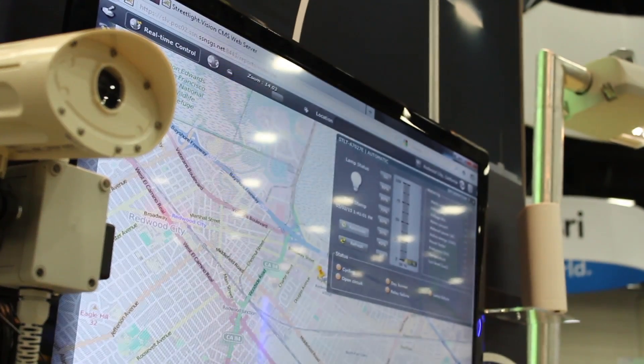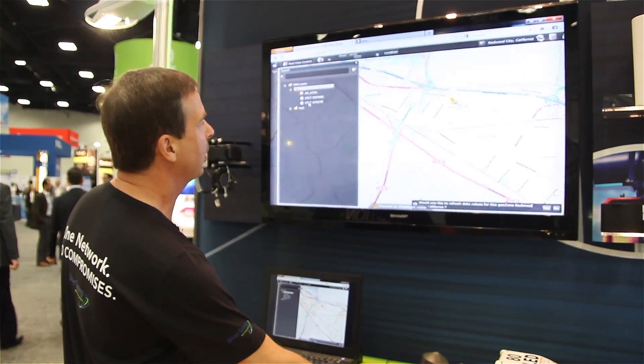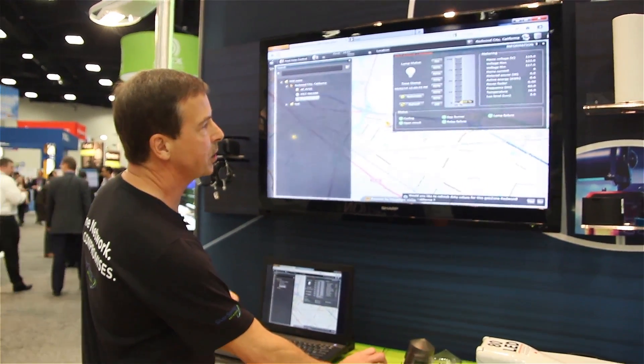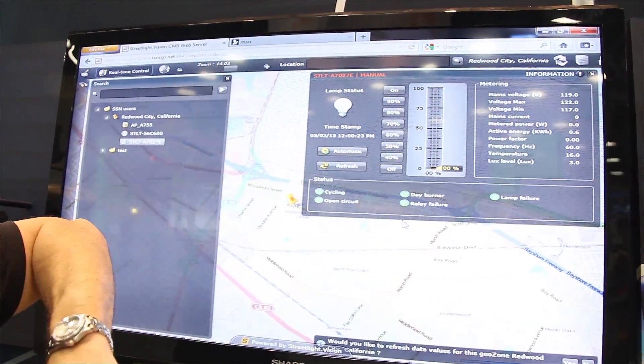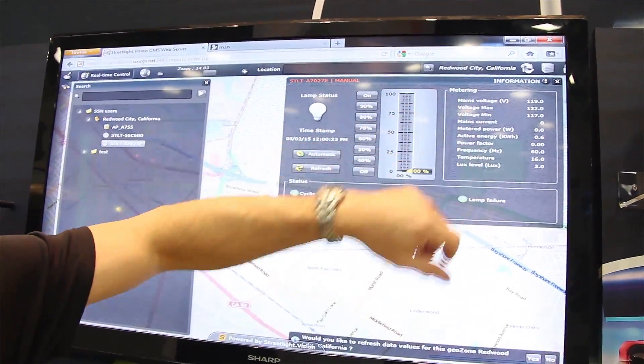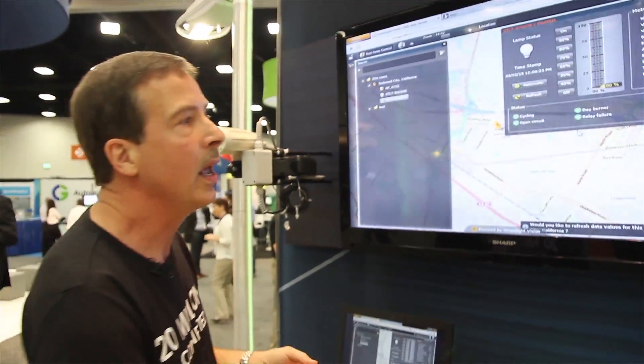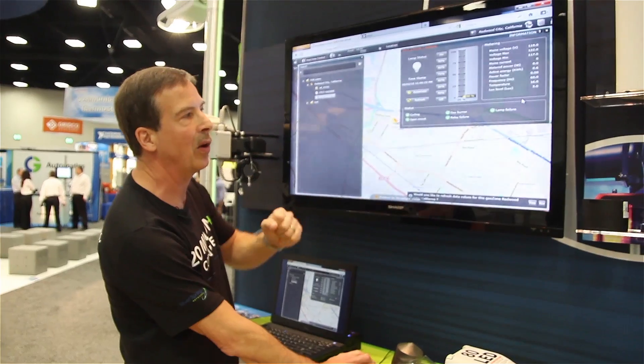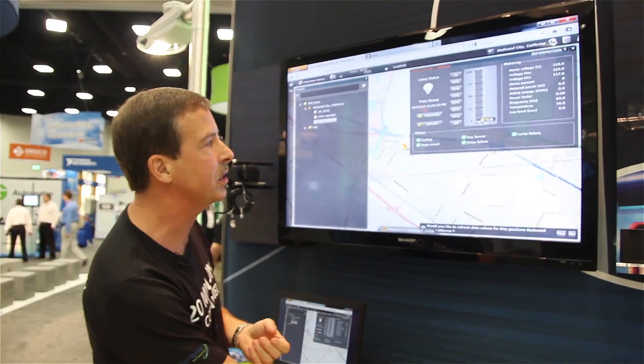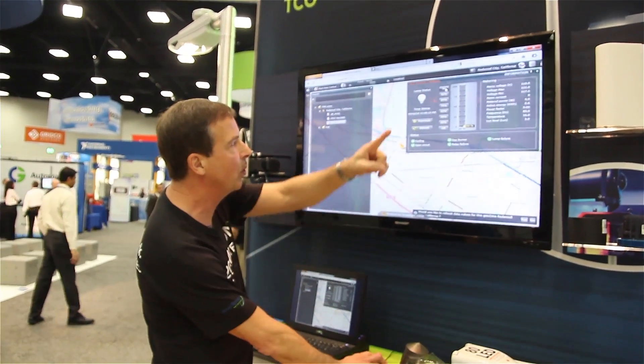We're going to click into the real-time control on this screen and identify the streetlight or group of streetlights we're interested in. On the screen here, I've got a streetlight that is currently off, and an indication of what percentage the streetlight is on. I've also got metering indication showing voltage — maximum and minimum voltage — giving utilities an idea of how voltage is being served to the streetlight, as well as metrics like power factor, temperature, ambient temperature, and the amount of lumens falling on the streetlight sensor. By clicking the on button, the software sends a signal through the network to the light and turns it on.